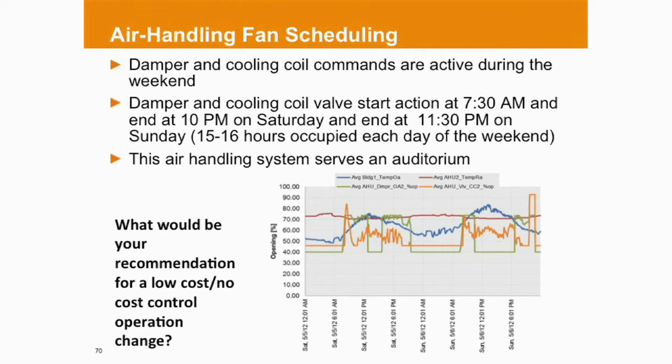And then that second bullet tells you some of the action with the dampers and cooling valves. They're basically active almost all day. There's only about 6 to 8 hours where they're reduced. And I'll tell you this much, which I thought was in our slide. Oh yeah, there it is, the third bullet. It's serving an auditorium. So we talked about auditoriums earlier, notorious for running 24/7 or almost 24/7, lightly occupied.